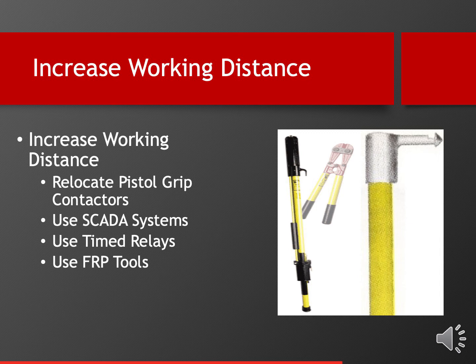And then the use of fiberglass reinforced plastic tools. These are the switch sticks you see here on the right. Typically, those are only used on high voltage circuits. But hey, if you're working on a piece of equipment that is set up to be using one of these devices, even adding an extra 2 feet will improve your situation dramatically. So increasing working distance is always a good option if you can. Let's go to the next slide.